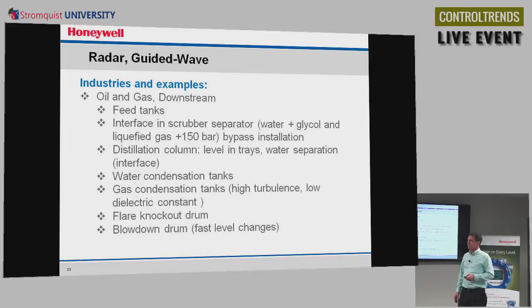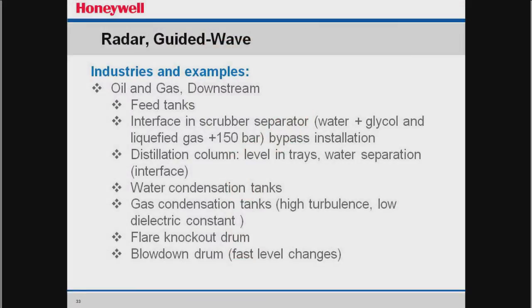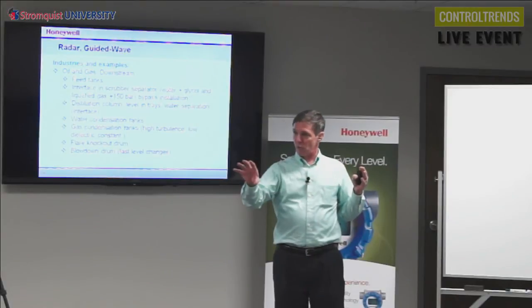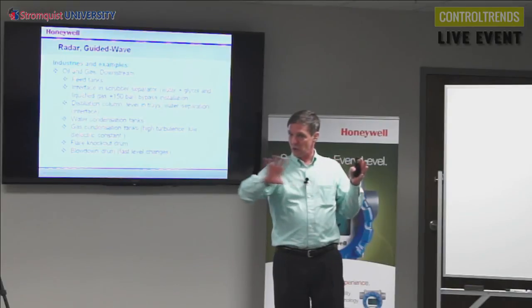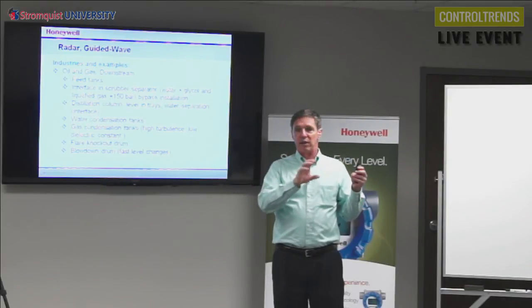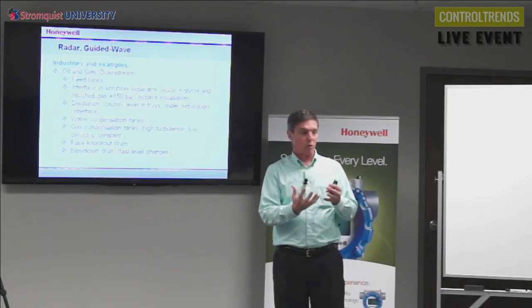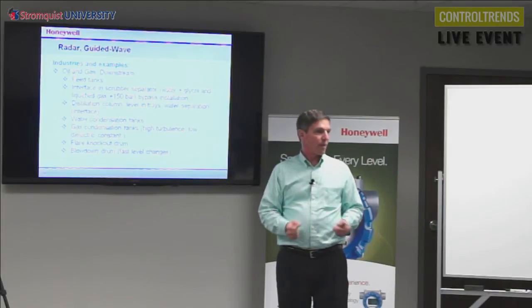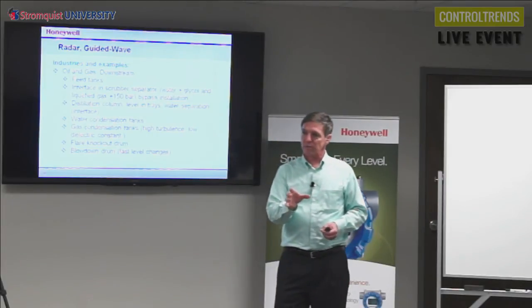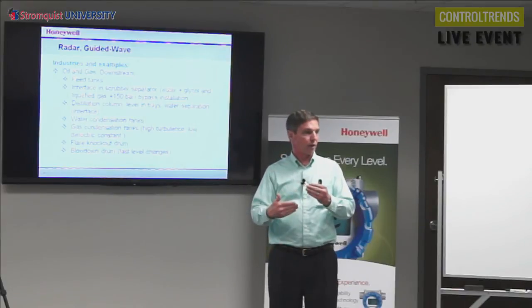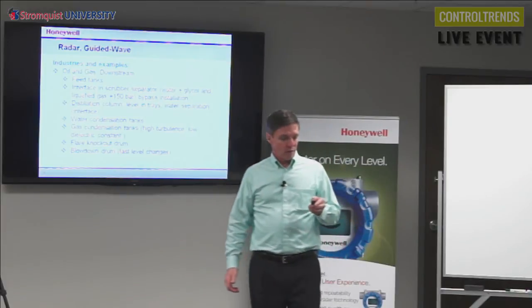Now, I'm talking about oil and gas downstream here. Specifically, that would be refineries. So it could be feed tanks, interface in a scrubber separator, the distillation column we've mentioned in the chemical industry too, across the trays, the water condensation, the gas condensation tanks, the flare knockout drums. So these flare knockout drums would be on a flare line. So where they're trying to flare off some waste product, it's typically a gas. It's going to go through a line before it goes to the flare to be burned. And you'll get condensation, and that'll be collected in these pots, or just sort of collection tanks. And so what they'll do is they'll measure the level in these pots, and as the level gets too high, they'll want to drain it. So they'll monitor that level to know when to drain the flare knockout drums.